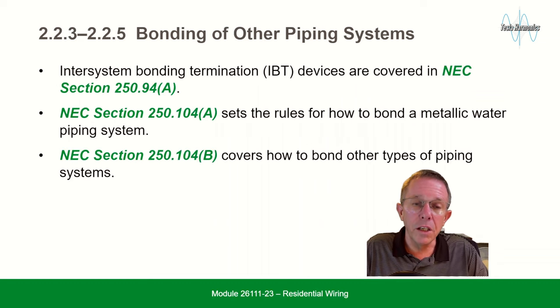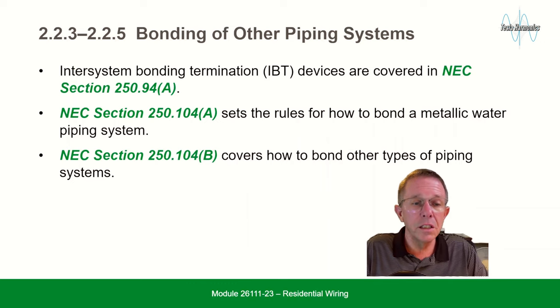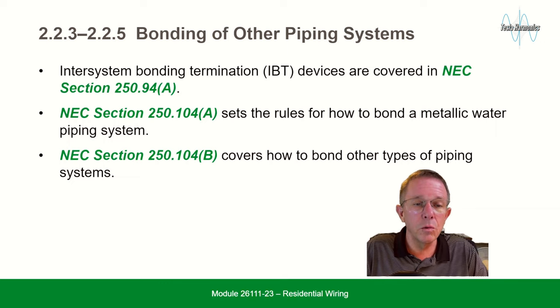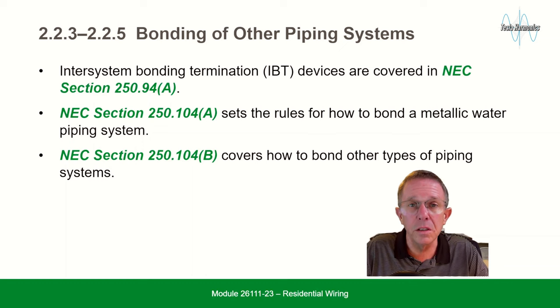Bonding of other piping systems: inter-system bonding terminations, or IBTs, are covered in NEC section 250.94(A). NEC section 250.104(A) sets the rules for how to bond a metallic water piping system, and NEC section 250.104(B) covers how to bond other types of piping systems.